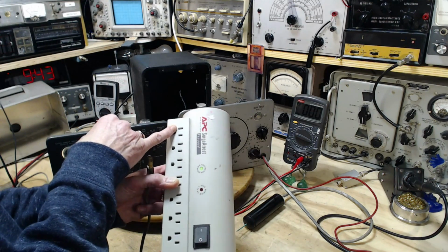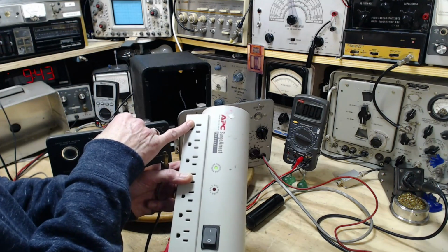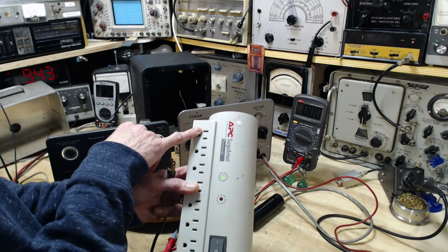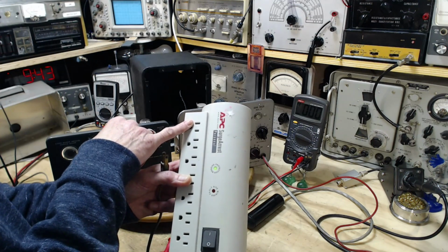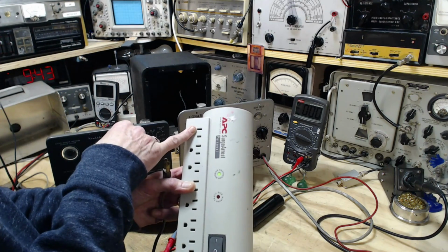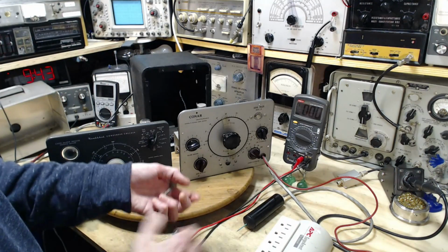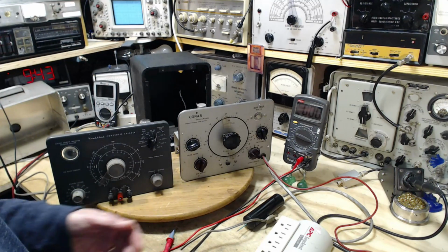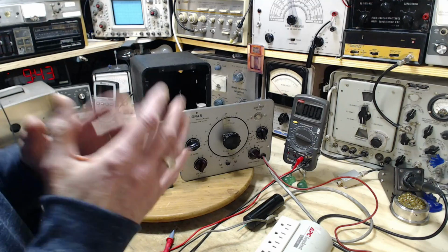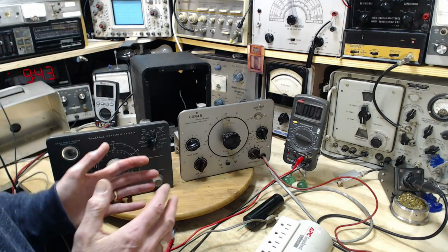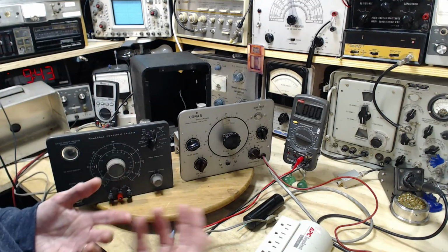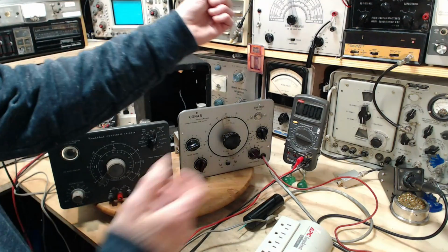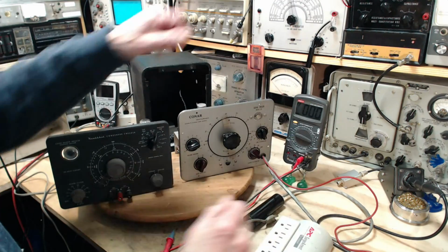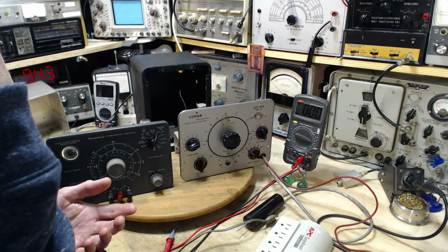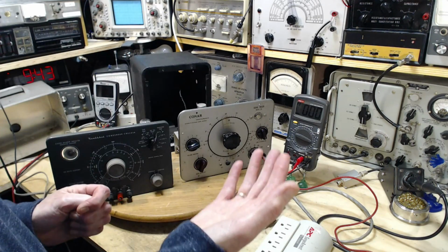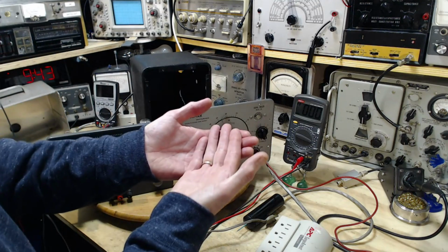Now there's another grounding that takes place in most houses, where a wire is run from the neutral in your fuse box as short as possible to the water service pipe coming into your house. A lot of people think that's to make contact with an earthed electrode, the water pipe. There's some truth to that, but it's really about making contact with all the piping in your house. The concern is, if you don't hook up the neutral to your water pipe, and somehow in your house a live wire, the black wire with 120 volts on it, touches a water pipe somewhere.